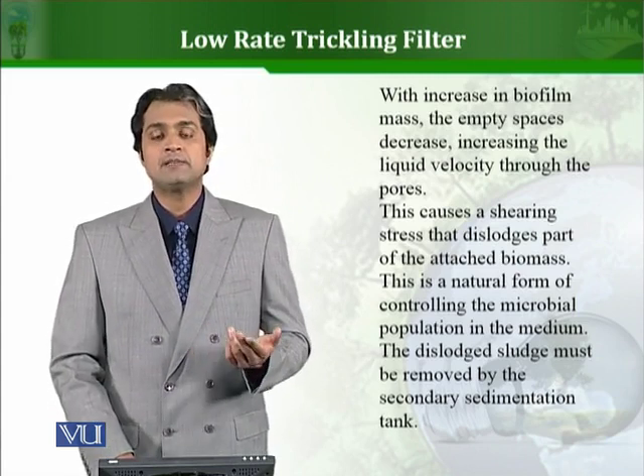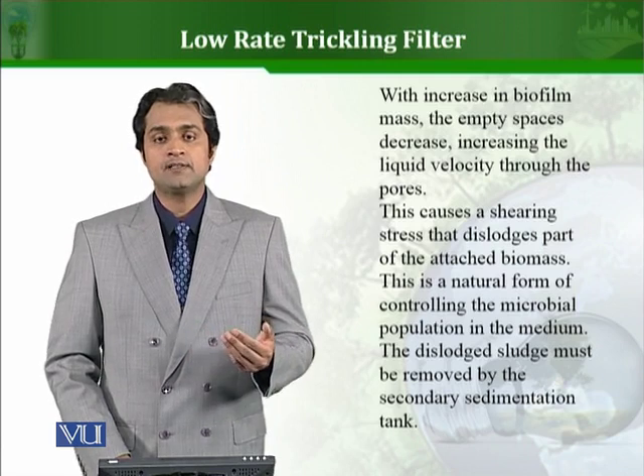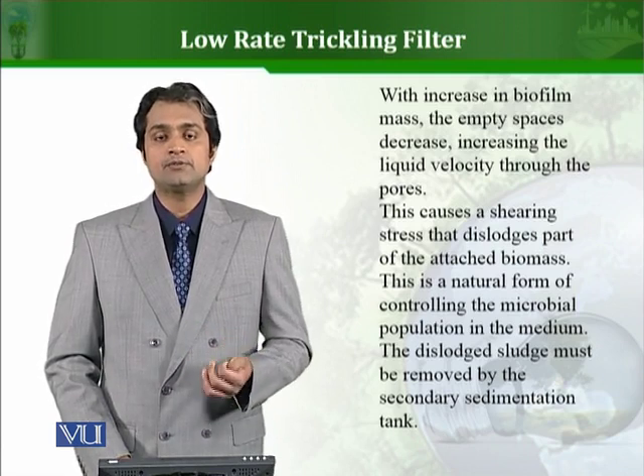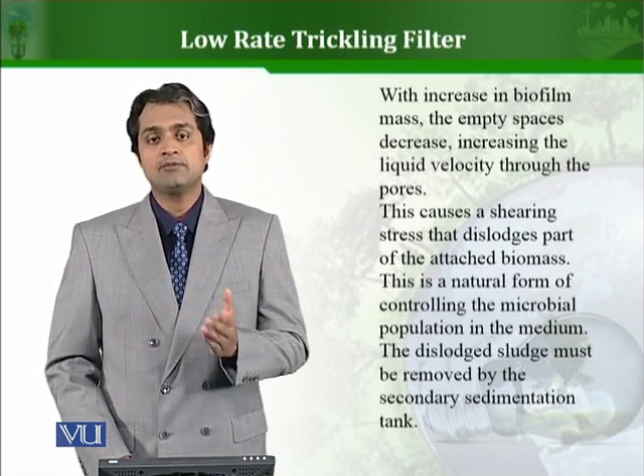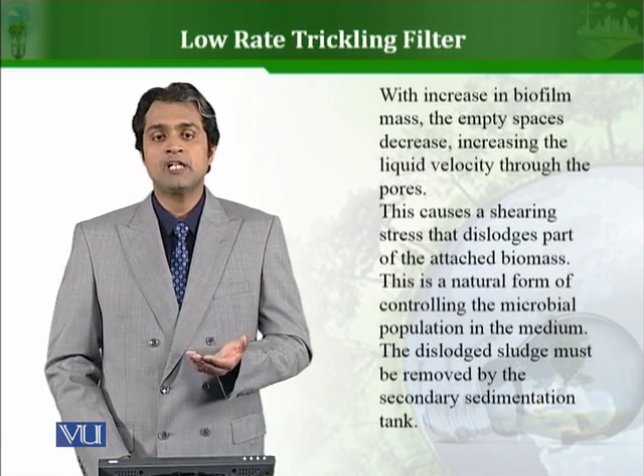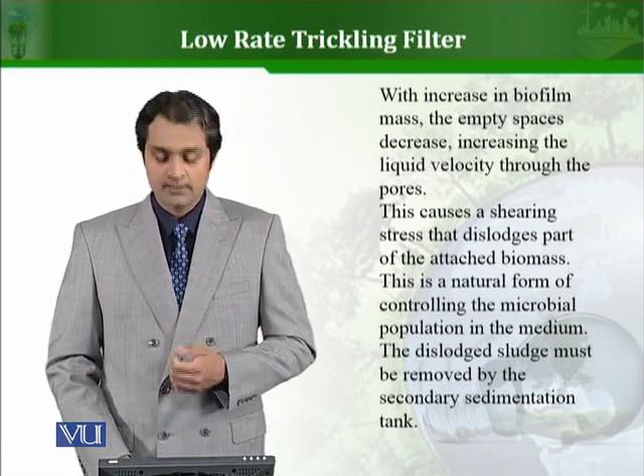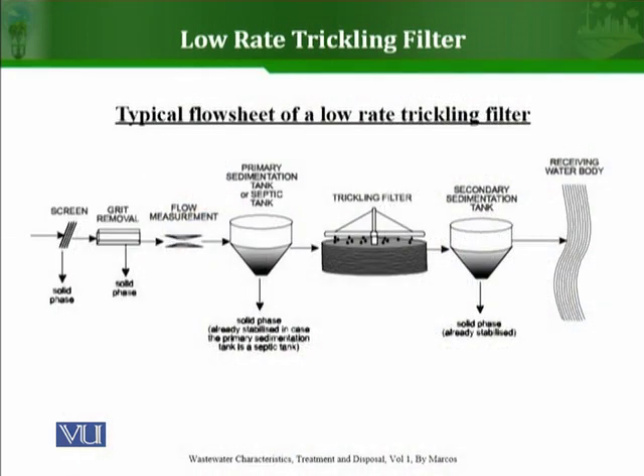The dislodged biofilm is then removed in a secondary sedimentation tank. We must ensure that the biomass used to treat the wastewater is removed before the treated effluent is released to the environment. A typical flow sheet of a low rate trickling filter includes: screening to remove solids, a primary sedimentation tank, the trickling filter itself, and then a secondary sedimentation tank to remove the biomass before the treated wastewater is released.